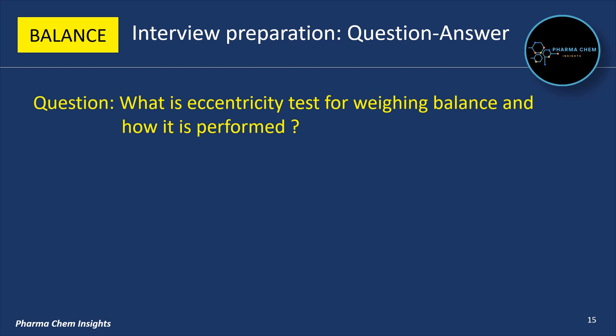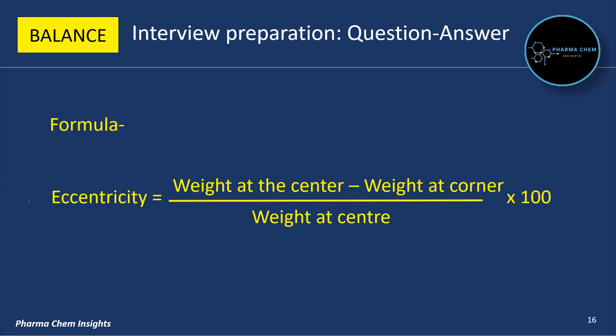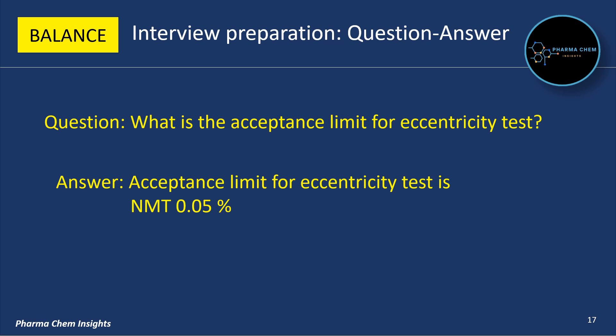Next question: what is the eccentricity test for a weighing balance and how is it performed? For the eccentricity test, a weight of more than 30% of the balance capacity is selected and placed at the centre and all corners of the weighing pan to check eccentricity. As you can see in the figure, 5 positions are used: position 1 at the centre, then positions 2, 3, 4, and 5 at each corner. The formula is: Eccentricity = ((Weight at Centre − Weight at Corner) / Weight at Centre) × 100. The acceptance limit for the eccentricity test is not more than 0.05%.